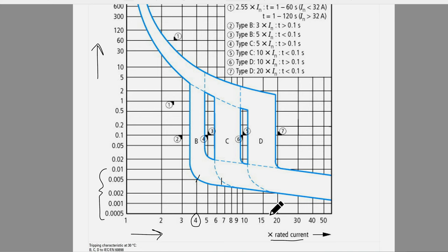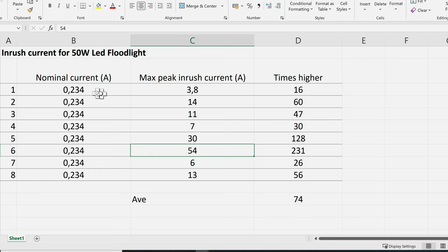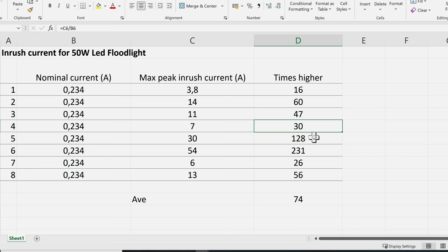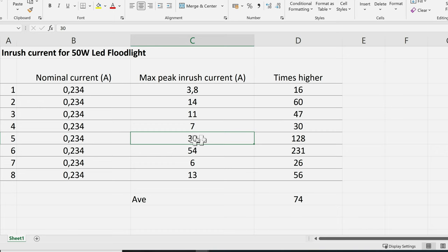Here are some values from measurements I've taken for inrush current on a 50-watt LED floodlight. The nominal or running current was only 0.234 amps, but the inrush current when I turned on that light was sometimes 16 times higher, sometimes 60 times, 47 times, 30 times, 128 times, and even 231 times higher. So one can see that the inrush current is many times higher than the nominal current.